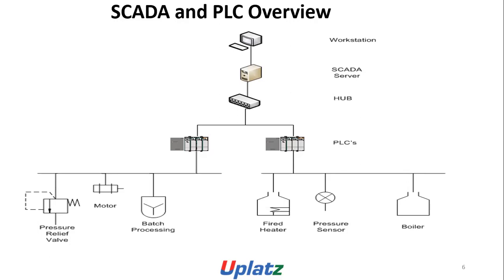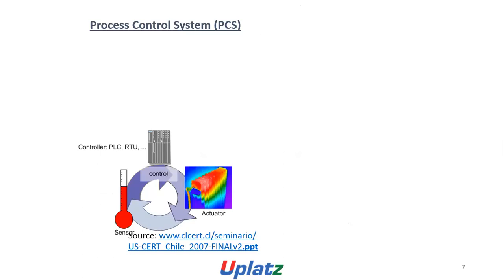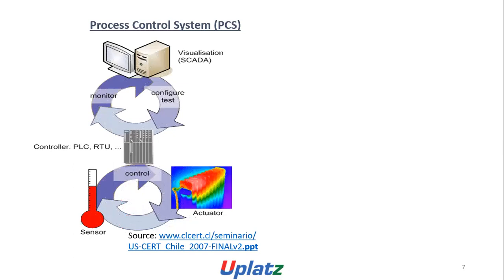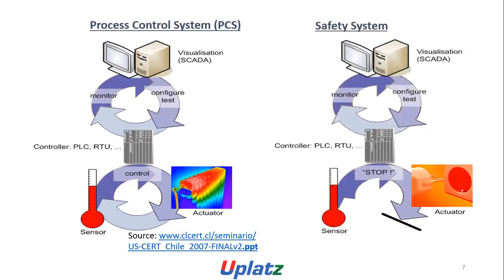The typical SCADA and PLC overview. Process control system, controller, PLC, RTU, control sensor actuators. Source is www.clcert.cl, seminario, US-CERT Chile, 2007 final version PPT. We have the visualization SCADA server, monitor and configure test. Safety system: we have the visualization SCADA, monitor, configuration test, the control here, and what are the various stopping mechanisms, actuators, sensors, controller, PLC or RTU.